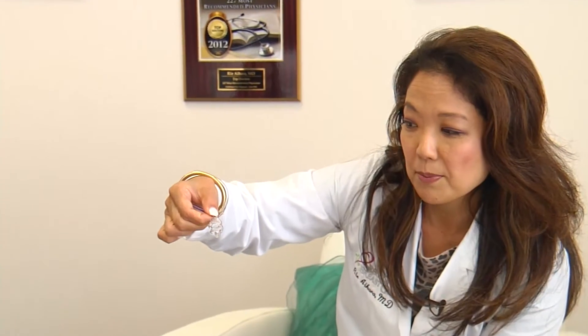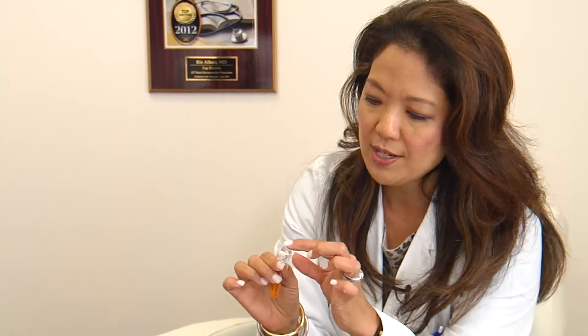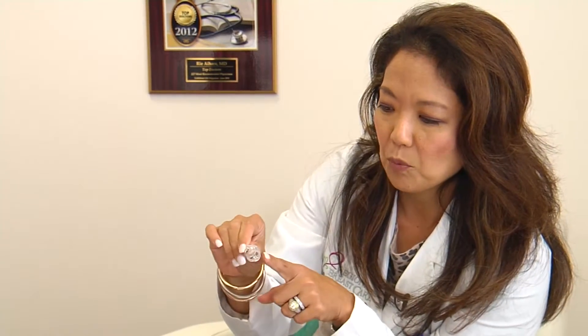While the titanium clips will remain in their established pattern, the plastic coil disintegrates over time. It's made of an absorbable material similar to what absorbable sutures are made out of. So within one year this plastic part will basically dissolve, and what you have left is the series of clips that are on the three-dimensional spiral.